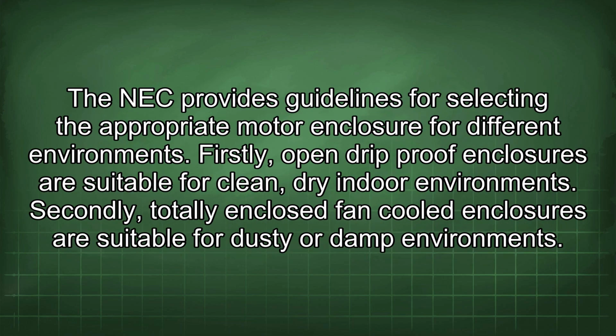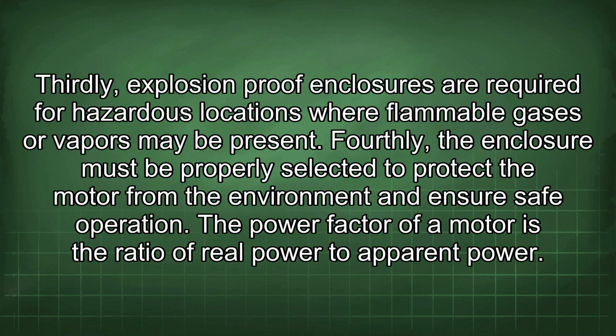The NEC provides guidelines for selecting the appropriate motor enclosure for different environments. Firstly, open drip-proof enclosures are suitable for clean, dry indoor environments. Secondly, totally enclosed fan-cooled enclosures are suitable for dusty or damp environments. Thirdly, explosion-proof enclosures are required for hazardous locations where flammable gases or vapors may be present. Fourthly, the enclosure must be properly selected to protect the motor from the environment and ensure safe operation.